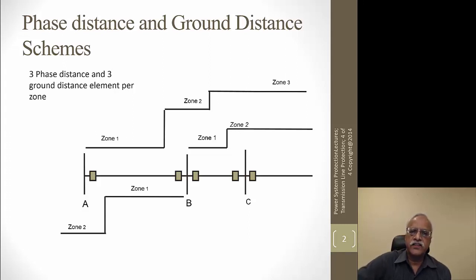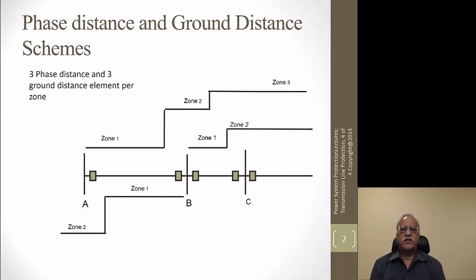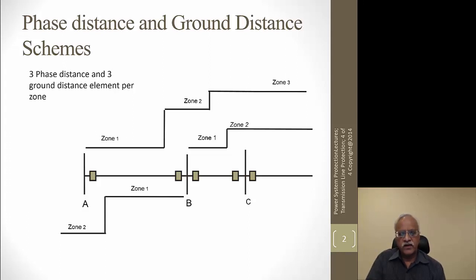Similarly, for a phase-to-phase fault element, it uses the voltage across the faulted phases Vab and the difference in currents Ia minus Ib, and takes the ratio of the two to measure the positive sequence impedance up to the fault point. The intent is to measure the positive sequence impedance up to the fault point so that when a fault occurs, irrespective of the type of fault, the relay can identify the fault location and take corrective actions accordingly.